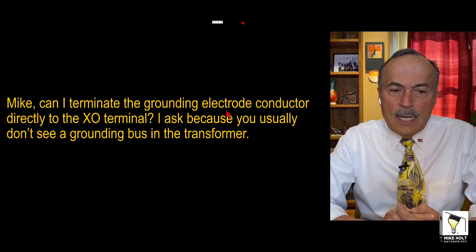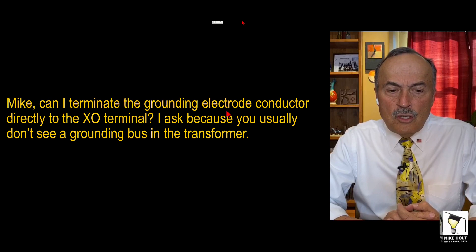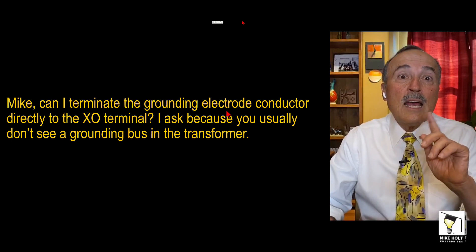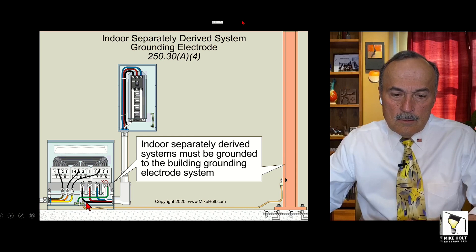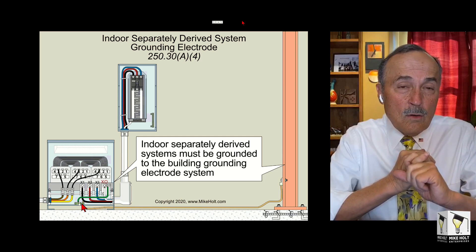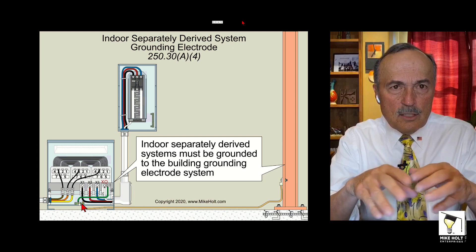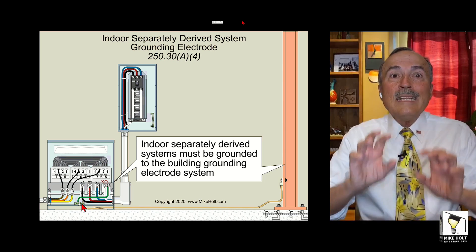Mike, can I terminate the grounding electrode conductor directly to the XO terminal? I ask because you usually don't see a grounding bus in the transformer. He sent me an email — I'm like, why are you asking me this question? Well, Mike, you know, it's usually not a grounding bus in the transformer. We're talking about the grounding electrode conductor. That grounding electrode conductor ultimately is going to go to the XO of the transformer — or maybe not XO because they could be different letters — but let's just say to the grounded point of the transformer, and that is for the purposes of grounding that system.